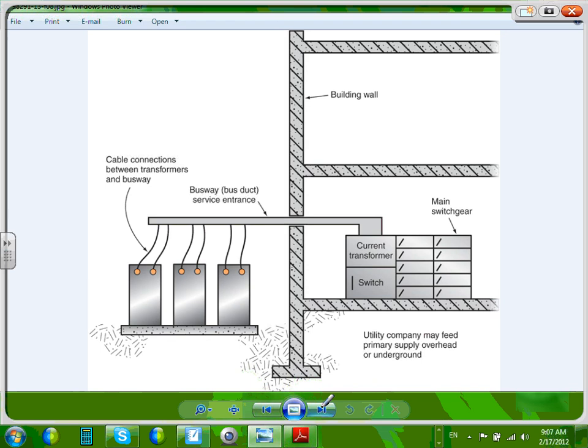Cable connection between transformers. Most of the time, when you bring power to the building, you bring it from a transformer owned and operated by the utility. So one way of bringing it into a commercial building is you bring current transformer switches. You can bring your feeder right in here into a legacy current transformer, meter the equipment, and then feed into your switch gear. If you're downtown Minneapolis, right here, that's probably how you're getting the power. You bring a busway like this or cables from underground vaults that are full of transformers, network transformers, and they pull them directly into your current transformer, so you can use CTs and PTs. This is how you can meter it to your main disconnect, right? And then you feed it down into your 4,000 amp switch gear. That's it. We call this one service entrance conductors.